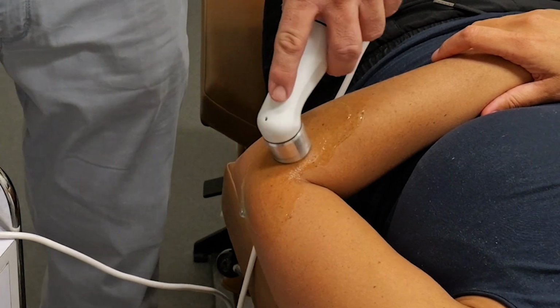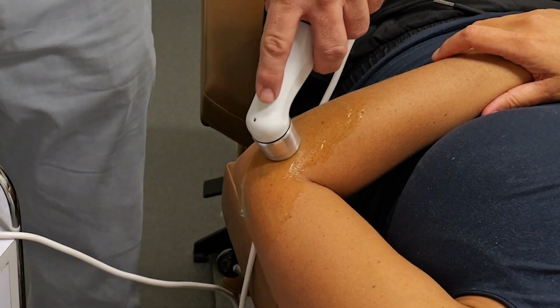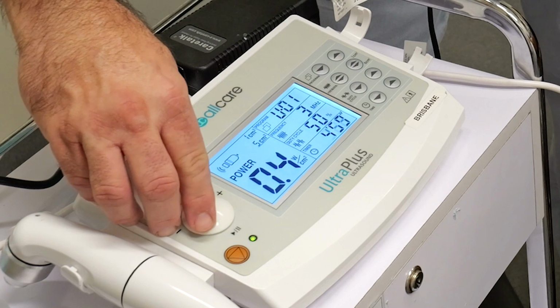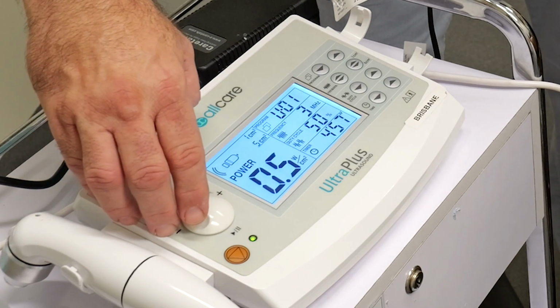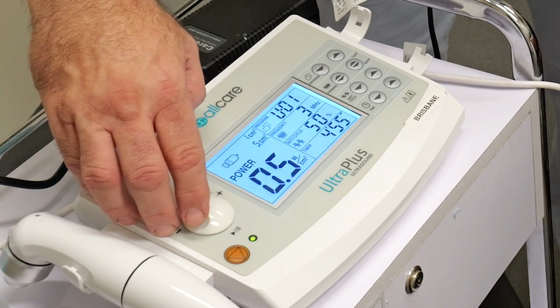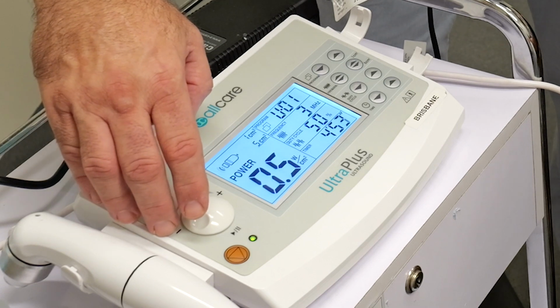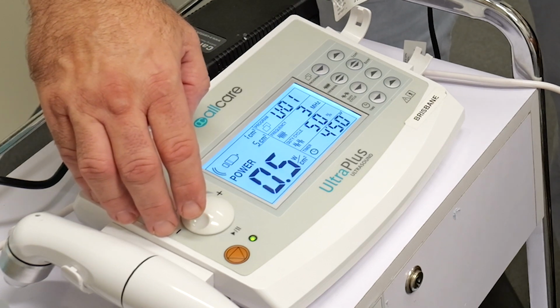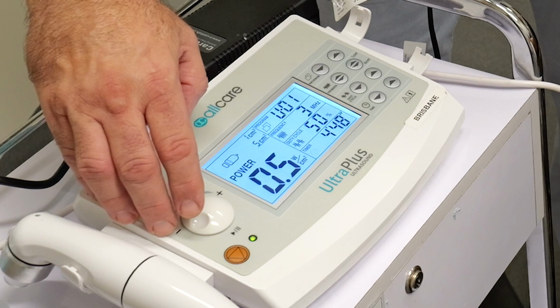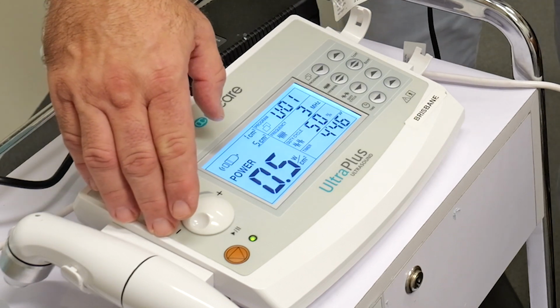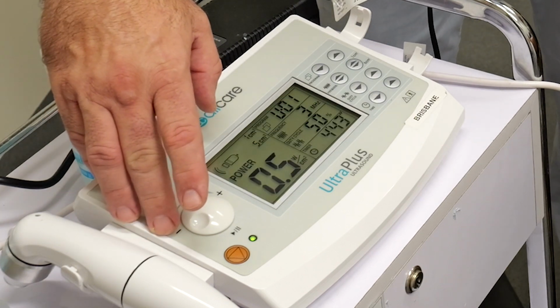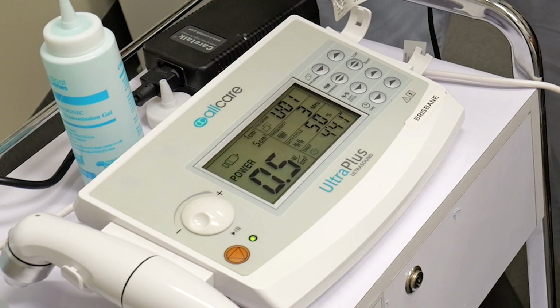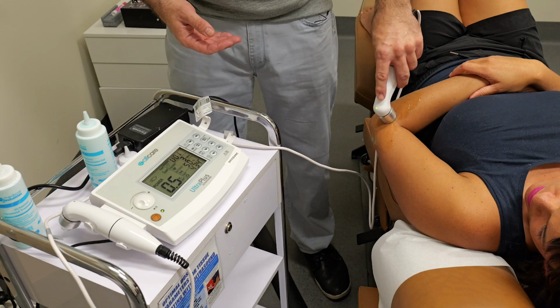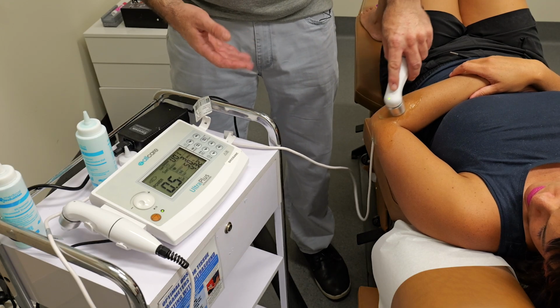Okay, so to get the machine going, very straightforward. We're just going to turn up this dial, and that's 0.5 watts per centimeter squared, and that's a reasonable starting point. In this case, in a young, healthy female, we can probably use a little bit more power with a healthy circulatory system. One of the things that you need to be concerned about with people that have compromised circulation is they can't get rid of the heat as easily. So you have to consider that when you're setting up the machine.